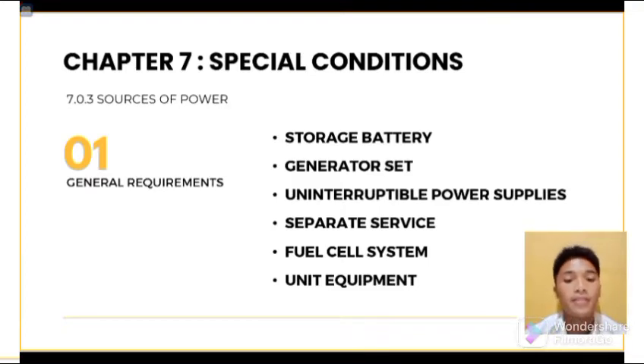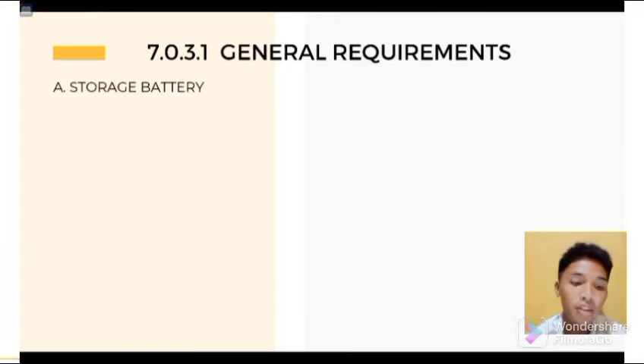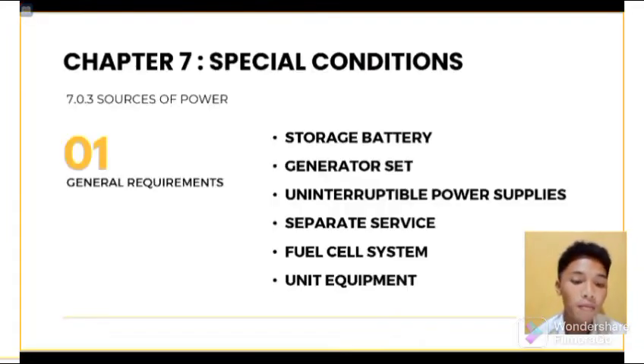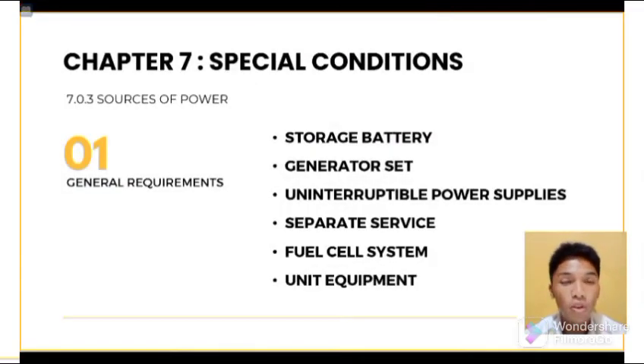Sources of power. Okay. 7.0.3.1 General requirements. Current supply shall be such that in the event of failure of the normal supply or within the building or the group of buildings concerned, emergency lighting, emergency power, or both shall be available within the time required for the application but not exceeding 10 seconds.